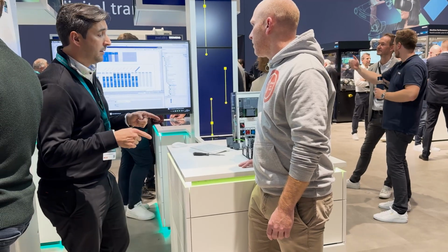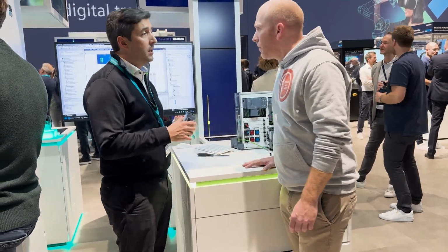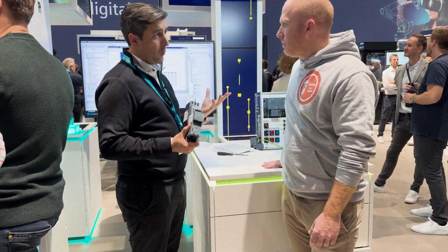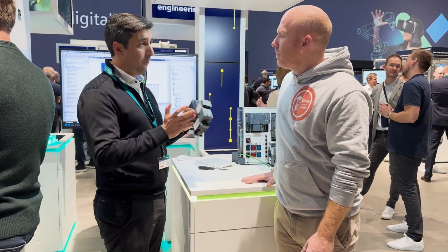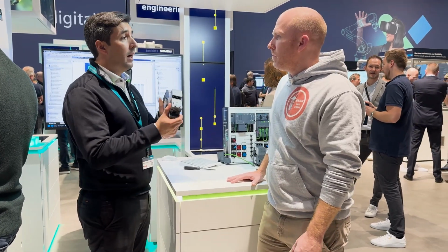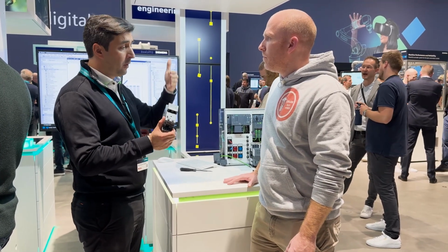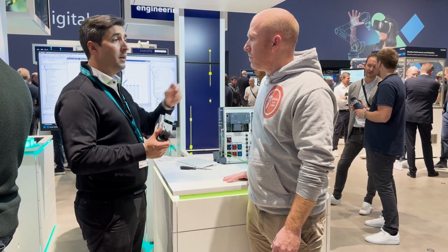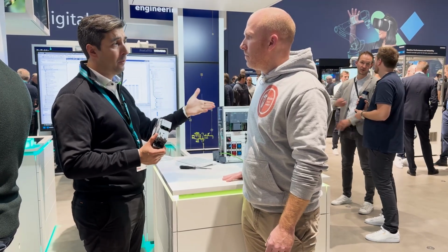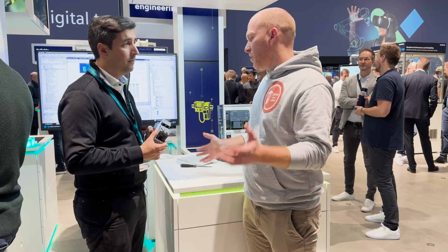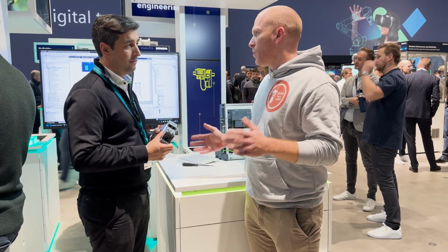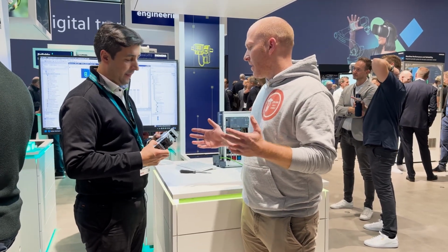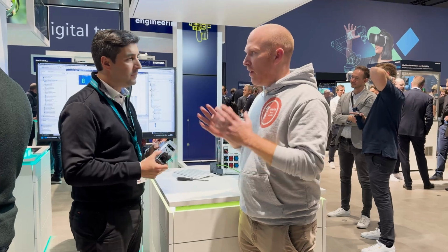Because one of the things that this device has is a very wide range. With two MLFBs, with two codes, you can go from 0.04 to 4 amperes. The second MLFB goes from 3.5 to 32 amperes. With two MLFBs, you can standardize your complete cabinet on the starters. Yeah, this is also important for the customer to save spare parts. Yeah. Because basically you just need two different devices to have a wide range covered.